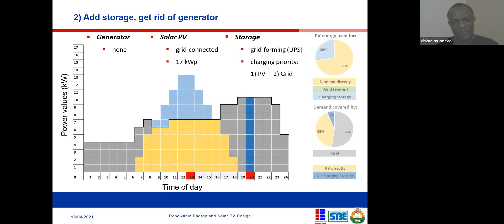This has to be done with caution because storage is very expensive, and that's why it's still important that you keep your generator until we achieve a breakthrough in storage technology. This explains how you can eliminate the use of your generator by integrating storage with your solar system and the grid. Three sources: the grid, your solar system, and your battery. If you integrate these three with a good control mechanism, you can get rid of your generator. But again, you have to do a cost-benefit analysis to know if it's worth it, or if keeping your generator makes more sense.